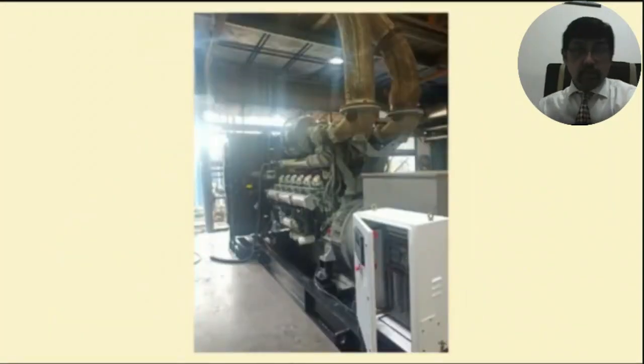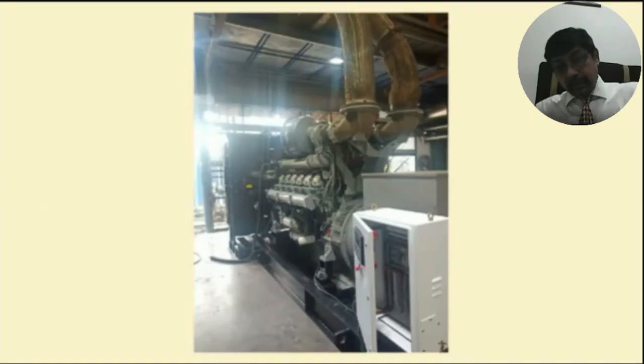So this, I can just show you this picture, which is very clearly showing the exhaust piping going up. These two pipes going up are basically the exhaust pipes. Now these exhaust pipes come out of the engine cylinders, and the smoke, the exhaust, the flue gases, what we call the emission levels, is taken over and left in the atmosphere. But in case the generator is above 1000 kVA, then this chimney has to be taken almost 30 meters in height and left in the atmosphere there, because this is the rule of CPCB, that is the Central Pollution Control Board.